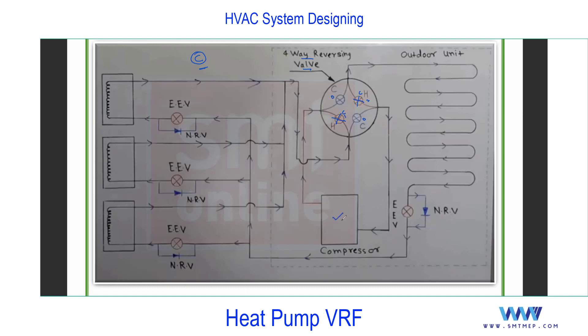The cycle starts from the scroll inverter compressor - same as what we discussed. The refrigerant leaves the compressor, passes through the open valve, and enters the condenser. After condensation, the refrigerant in liquid form passes through a bypass line with the NRV. It will not flow through the electronic expansion valve at this point - that EEV is in closed position in cooling mode.